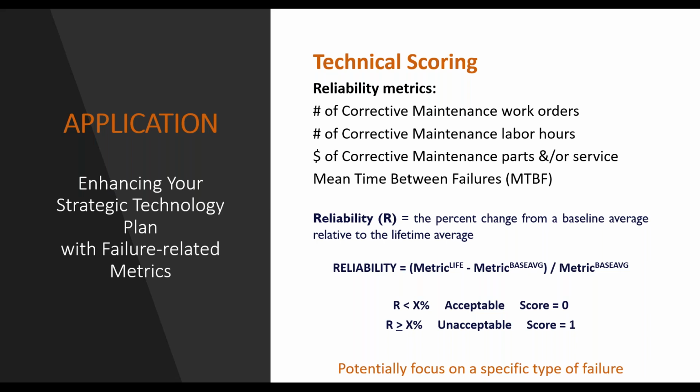How much of that change is acceptable? I mean, this is normalized, right? Think about your HTM procedures, your validation procedures. There's a tolerance. It could be plus or minus this many millivolts or millibars or whatever. Same thing here: a change in this reliability metric should be contained within a tolerance zone. What is that percentage? Again, this is unique to your organization's risk tolerance. How much risk is your organization able to handle? It might be a 10% change, it might be a 2% change.